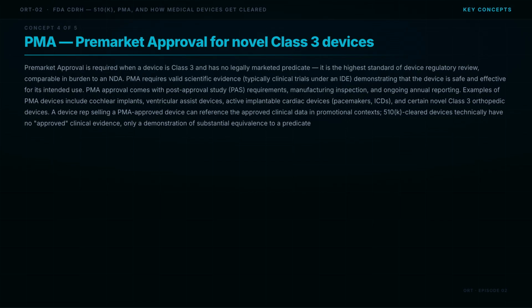PMA requires valid scientific evidence, typically clinical trials under an IDE, demonstrating that the device is safe and effective for its intended use. PMA approval comes with post-approval study requirements, manufacturing inspection, and ongoing annual reporting. Examples of PMA devices include cochlear implants, ventricular assist devices, active implantable cardiac devices, pacemakers, ICDs, and certain novel Class III orthopedic devices. A device rep selling a PMA-approved device can reference the approved clinical data in promotional contexts. 510K cleared devices technically have no approved clinical evidence, only a demonstration of substantial equivalence to a predicate.